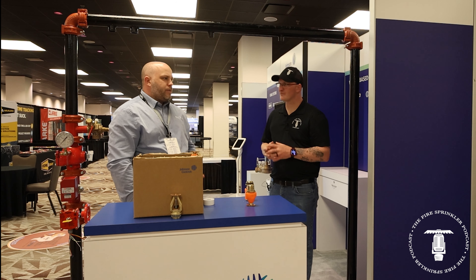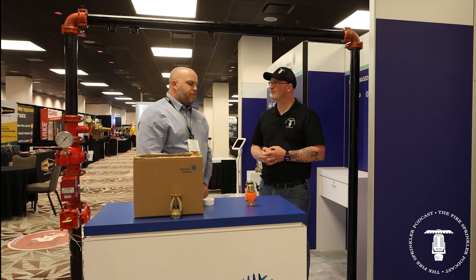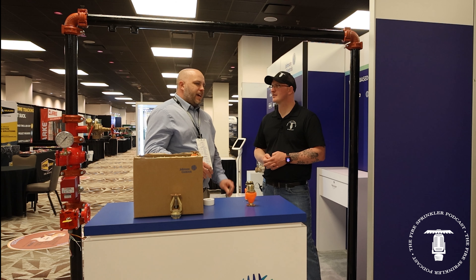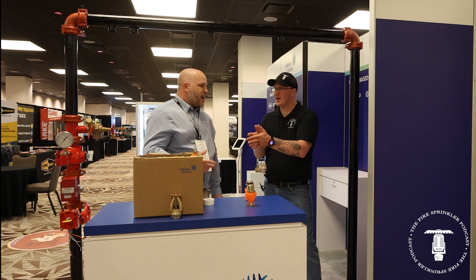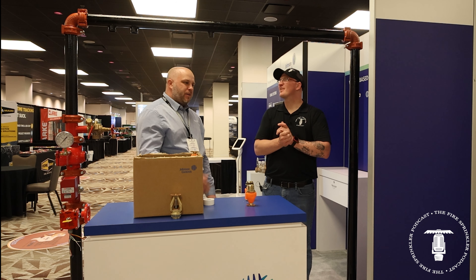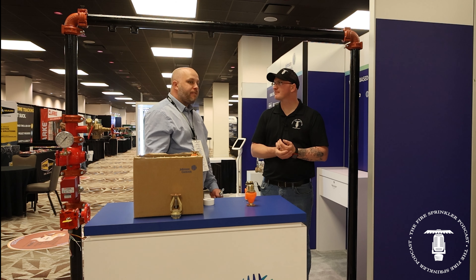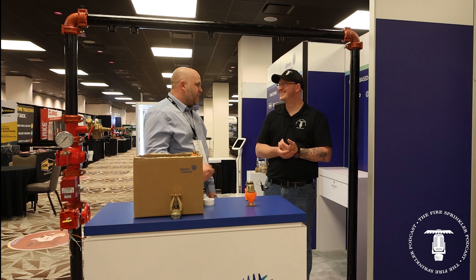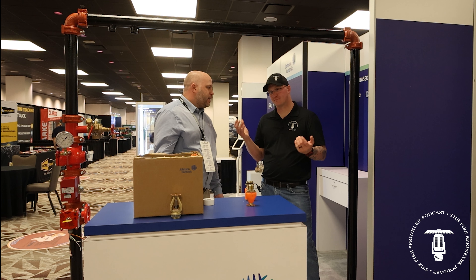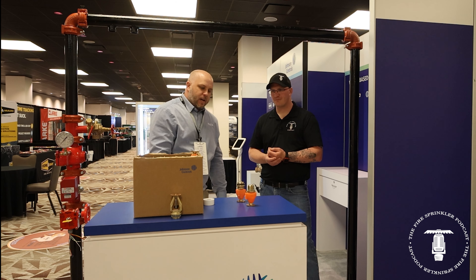That's kind of an anomaly that's pretty much standard on all ESFR one-inch installs. I was a fitter for 10 years, and I've heard people say 'I don't have leaks' — but in that time I know I installed at least 10,000 to 15,000 sprinklers. Every system was the same: I'd put on my hydro, go to lunch, come back, and find two to three heads that I'd have to drive my lift two to four miles per hour to, go up, tighten another half turn, and then hope I didn't break a head — because by that time a lot of those caps are already gone and in the trash somewhere.